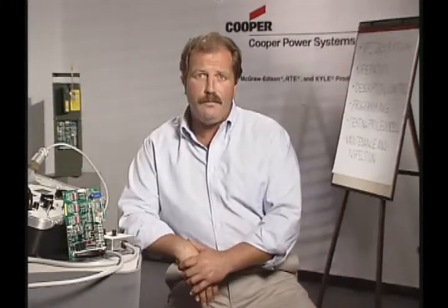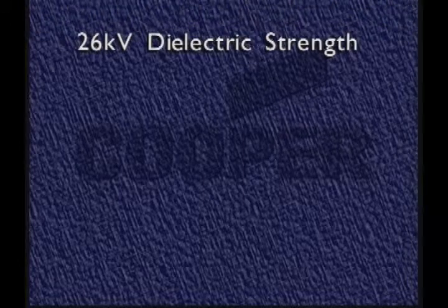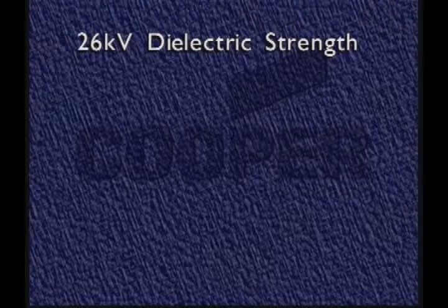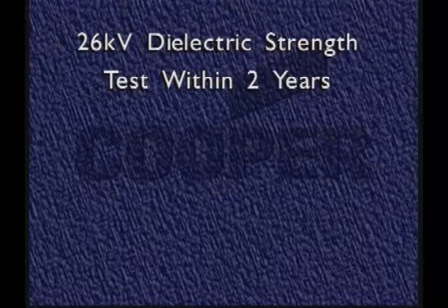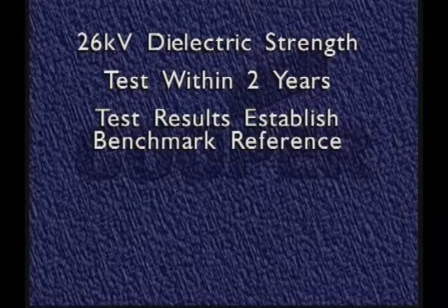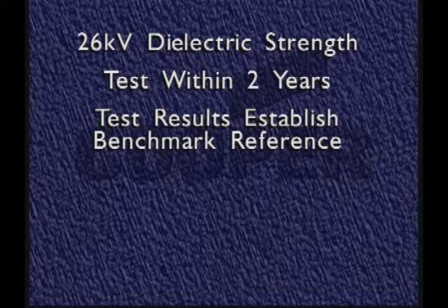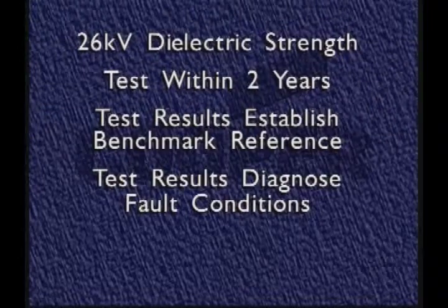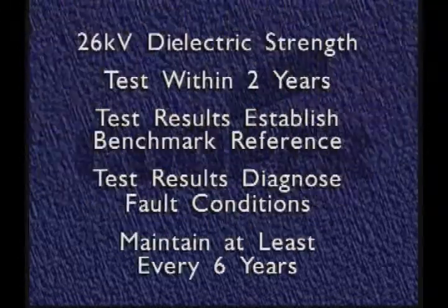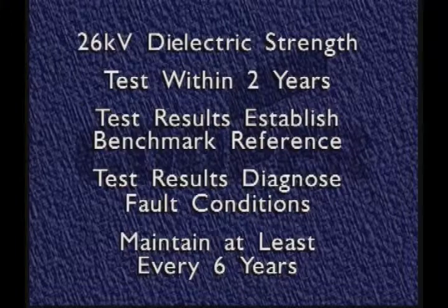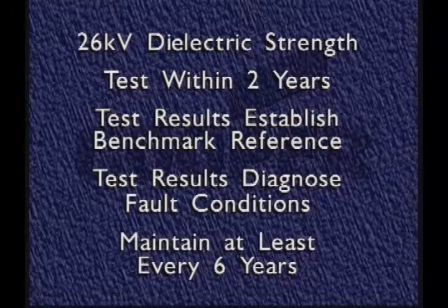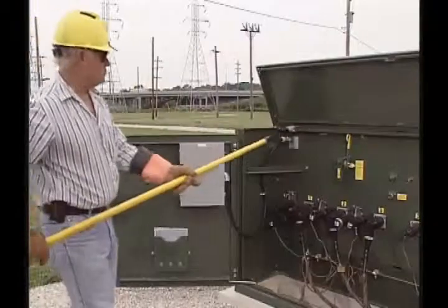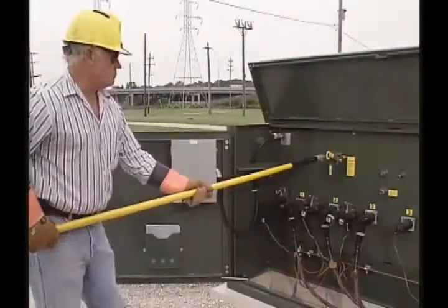A routine maintenance inspection program is required to ensure proper operation of the Kyle vacuum fault interrupter. The insulating oil must have a minimum dielectric strength of 26 kV and should be tested within 2 years after the installation of the unit. These test results will establish a benchmark reference for observing trends in the unit's normal operation and to diagnose any fault conditions that may be present. After the initial oil testing and inspection, the VFI should be maintained at least every 6 years. However, we recommend regular external inspection of the VFI.